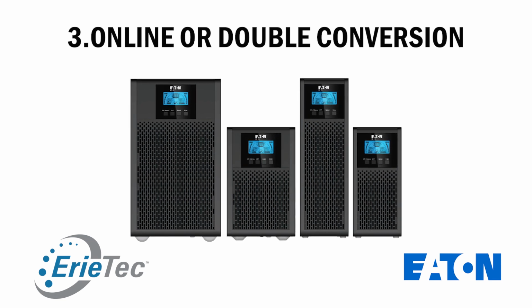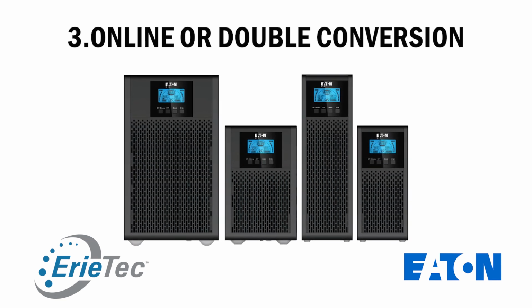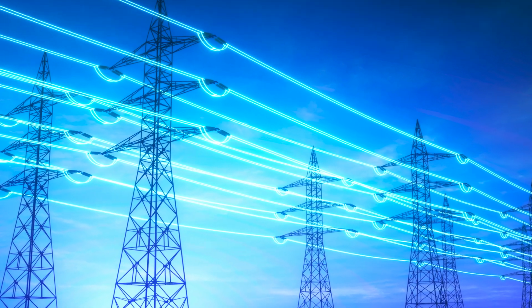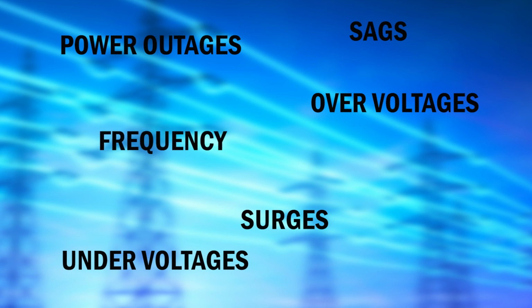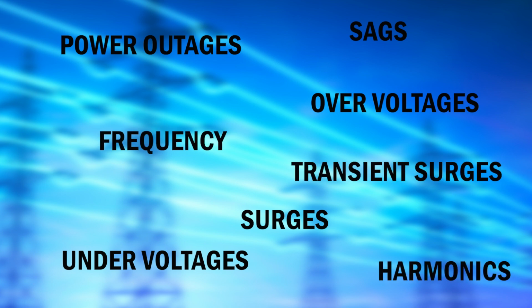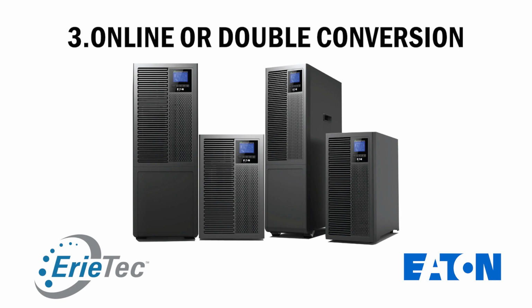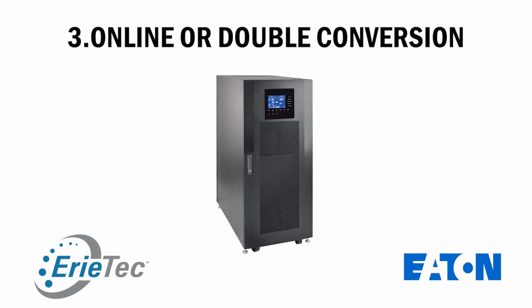The third type of UPS is called online or double conversion. This type of UPS is completely different from the other two. It takes the incoming power and rectifies it. So between the rectifier and the next stage, the inverter, we've got DC power. At that point is where the batteries are connected, and then the inverter creates a brand new sine wave to the output. So it can handle any kind of power quality issue, from power outages, surges, sags, overvoltages, undervoltages, frequency, any kind of harmonics, and transient surges. So it basically acts as a power conditioner with a battery backup. So you get totally clean power at the output. It's the most popular UPS, and all three-phase UPSs that Eaton makes are true online double conversion. So that's for the basics.